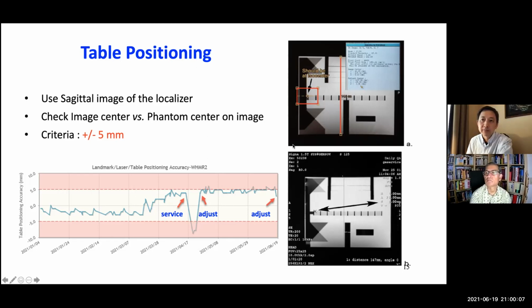That's the idea. Okay, if we landmark at the center of the phantom, then on the image, the center of the phantom or the laser landmark should be at the center of the FOV. If it's not, then the laser has an issue, right? So actually this test doesn't require the ACR phantom. We can use any phantom, just make sure we laser landmark at the center of the phantom. Then that can be tested. But here I'm showing the ACR phantom.